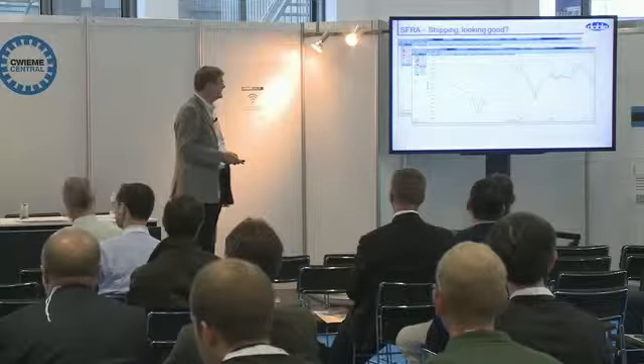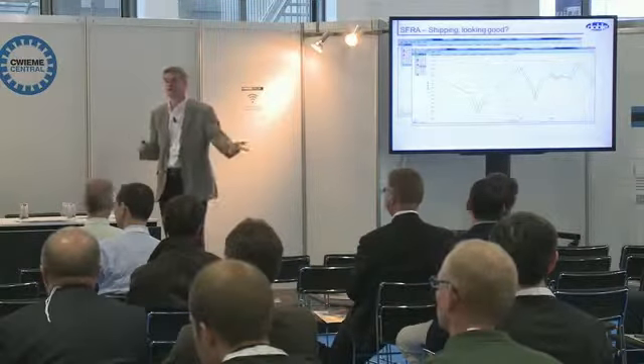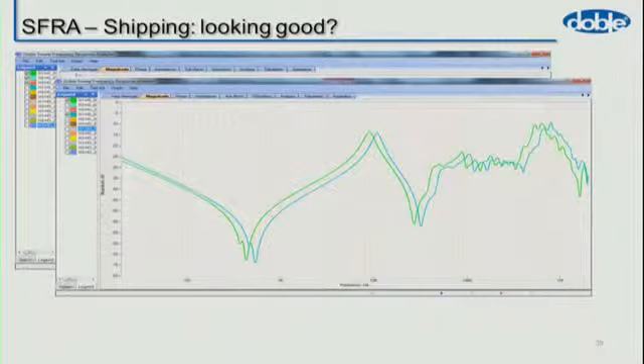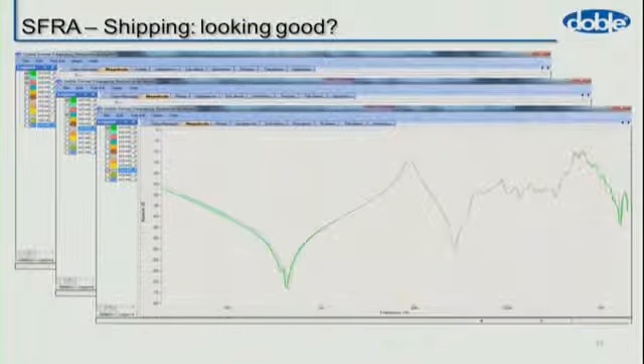If you know what you're doing, you can tell it's a three-phase. You can tell which phase is which. You know it has the expected shape. It looks like you'd expect. There are differences at high frequency. It may be due to asymmetry in the design. It may be due to some grounding variation. In the factory and in the field, are these acceptable? When you know that one's with oil and one's without oil, you've changed the capacitance, the resonant frequency due to the LC combination is shifted, they're acceptable.